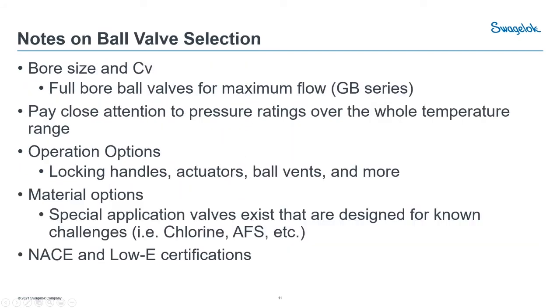Some final notes on ball valve selection — a bit on bore size and CVs. Remember, not all ball valves are full ported. The CVs can be lower on the 83 series because of the orifice size. A full bore ball valve is your best option for maximum flow — that's our GB series, a newer application that can go up to 6,000 PSI and has full bore available for full flow through your line size. If you're going for a high CV and large amount of flow, full bore is the way to go. Always check your CV to make sure you're not limiting your system flow, especially with orifice-drilled ball valves.